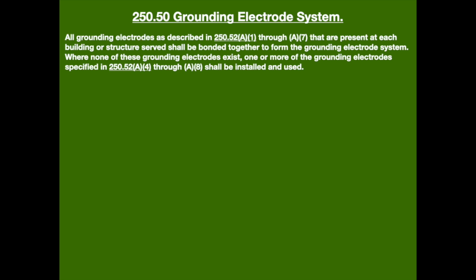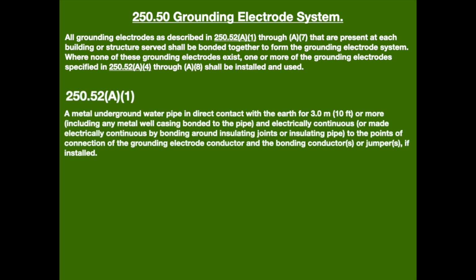The grounding electrode system. All grounding electrodes as described in 250.52(A)(1) through (A)(7) that are present at each building or structure served shall be bonded together to form the grounding electrode system. Where none of these grounding electrodes exist, one or more of the grounding electrodes specified in 250.52(A)(4) through (A)(8) shall be installed and used. A metal underground water pipe in direct contact with the earth for 10 feet or more, including any metal well casing bonded to the pipe and electrically continuous or made electrically continuous by bonding around insulating joints or insulating pipe to the points of connection of the grounding electrode conductor and the bonding conductors or jumpers if installed.